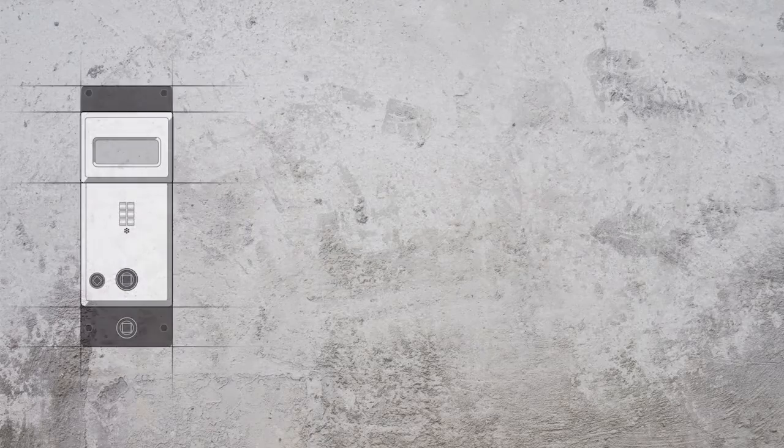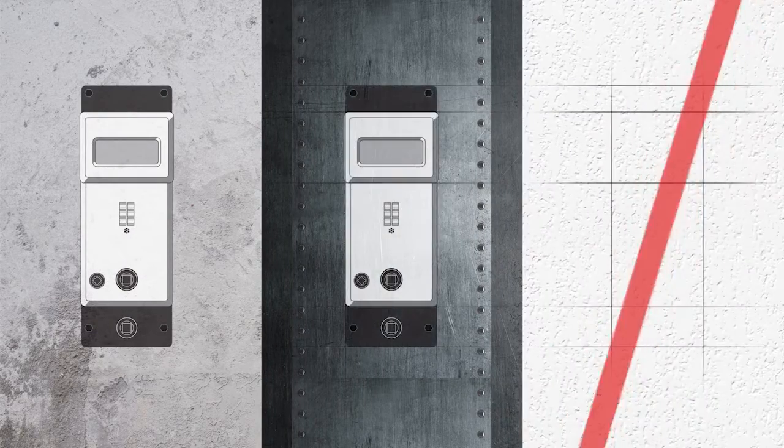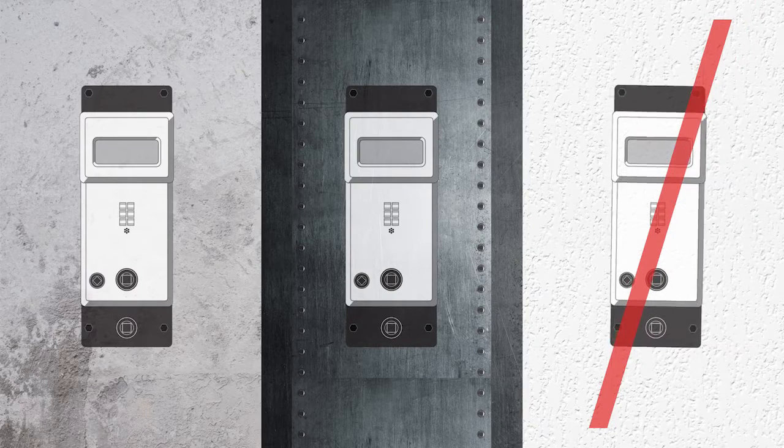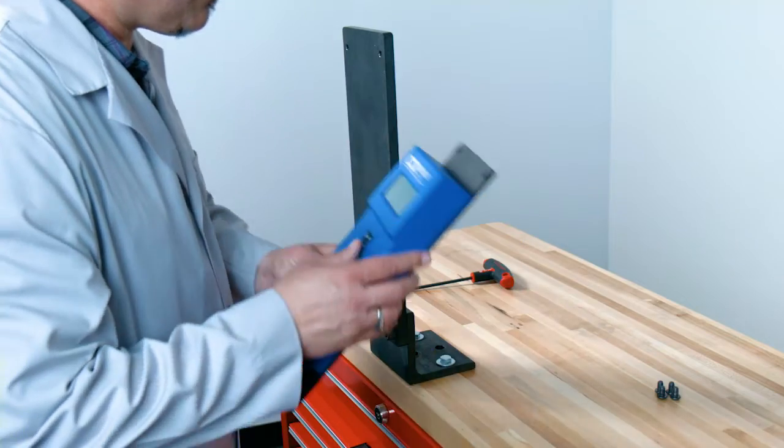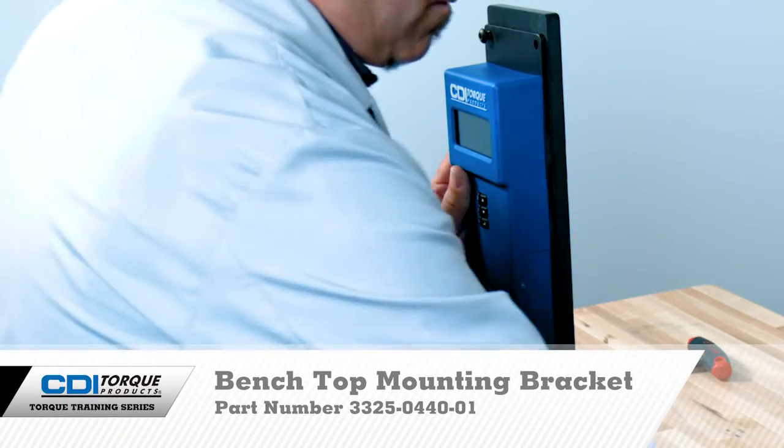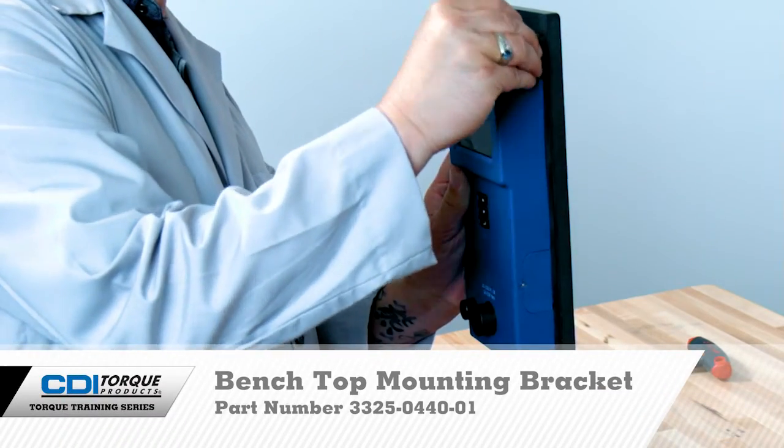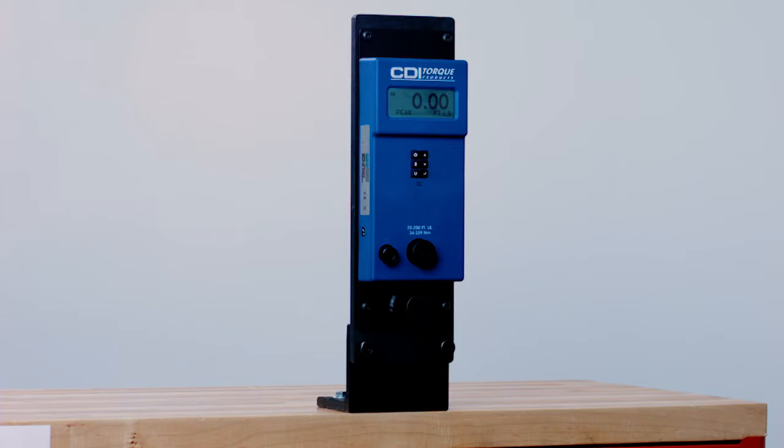Mount the DTC on a sturdy wall such as concrete or on a steel beam. Do not mount on unsupported drywall. For ease of use, mount the checker with the socket approximately waist-high to the user. Snap-on also has a bench top mounting bracket available for the DTC, part number 3325-0440-01.